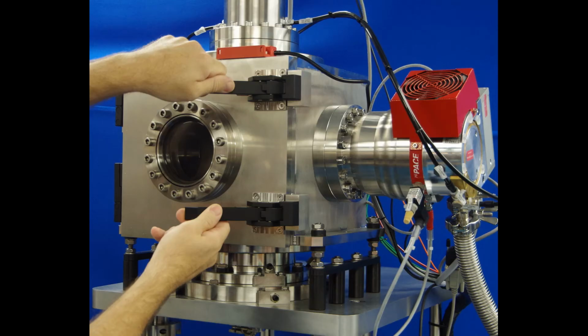Before opening the chamber door, confirm that the vacuum system is switched off and that the chamber has vented back to atmospheric pressure. Lift the two handles to disengage the locks. If there is no vacuum, the handles will lift freely. If the chamber is still under vacuum, they will not. Do not try to force them.